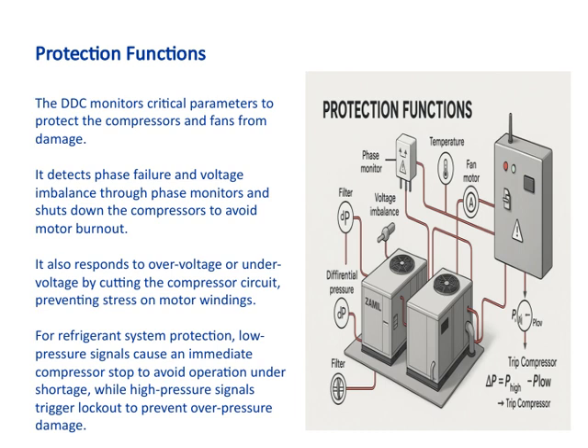Differential pressure sensors help identify filter clogging, and they delay the start sequence to prevent coils from freezing, which can cause serious operational issues. Lastly, the DDC continuously checks the entire communication and sensor system, raising fault alarms whenever a malfunction occurs. An example of a protection formula is delta P equals P high minus P low. If this pressure difference exceeds a set limit, the system will trip the compressor to protect the equipment.